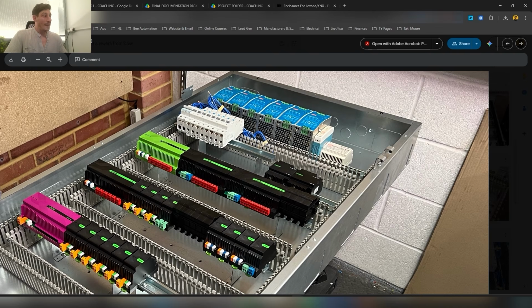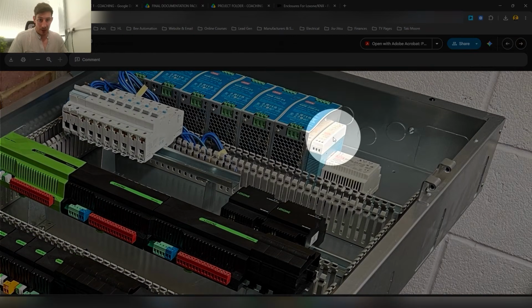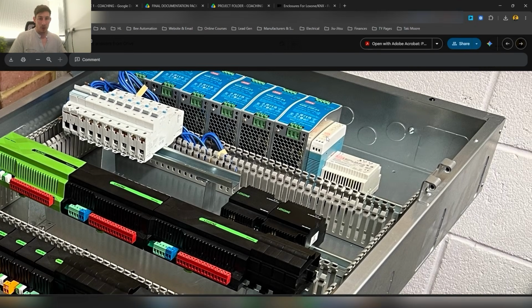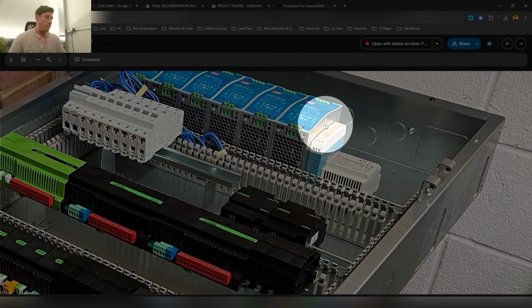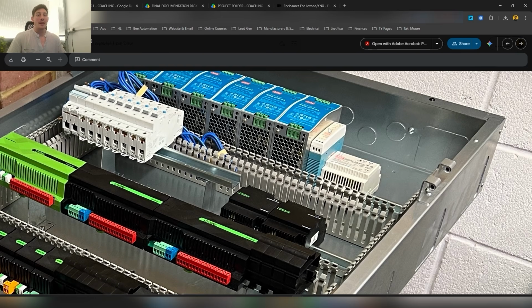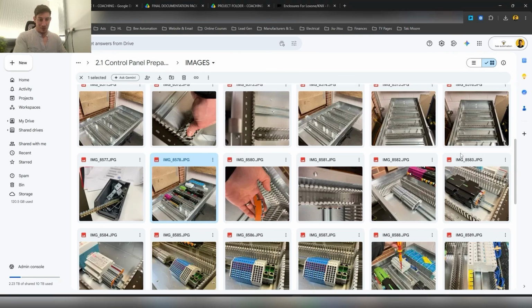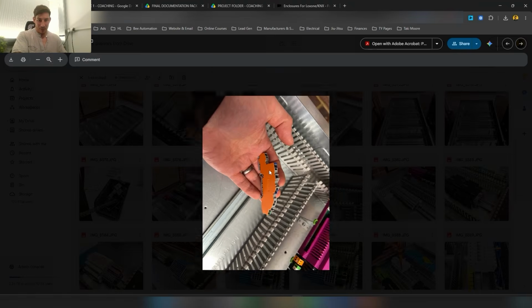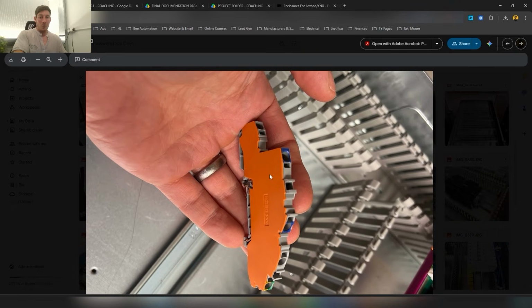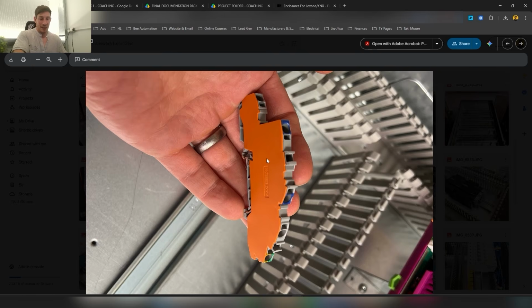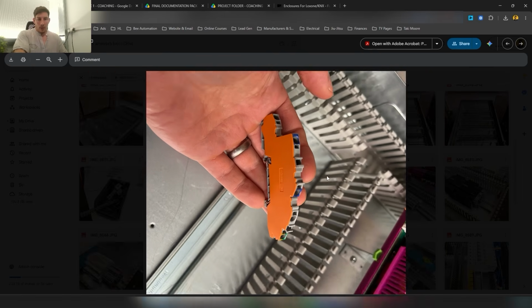We were using these metal cased PSUs, and had some terminal blocks right up against this metal plate, where this other PSU is. I wasn't using one of those blanking plates I just showed you on the terminal blocks, and the internals were shorting out against the metal casing. We had to fault find it for like half an hour, and finally realized it was that shorting out. So the little tip is: use those blanking plates for safety, but also for making your lives easier, reducing any potential faults that might creep in.